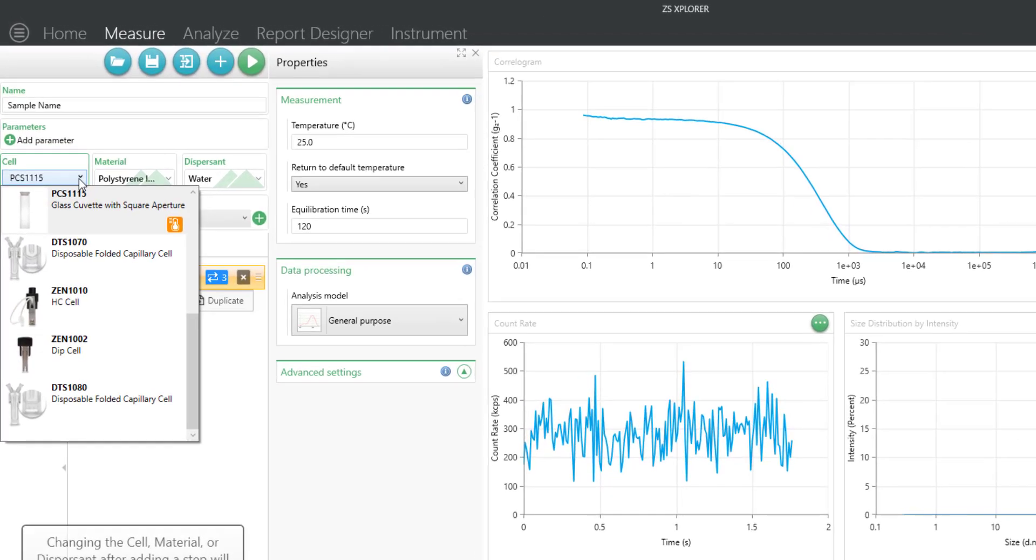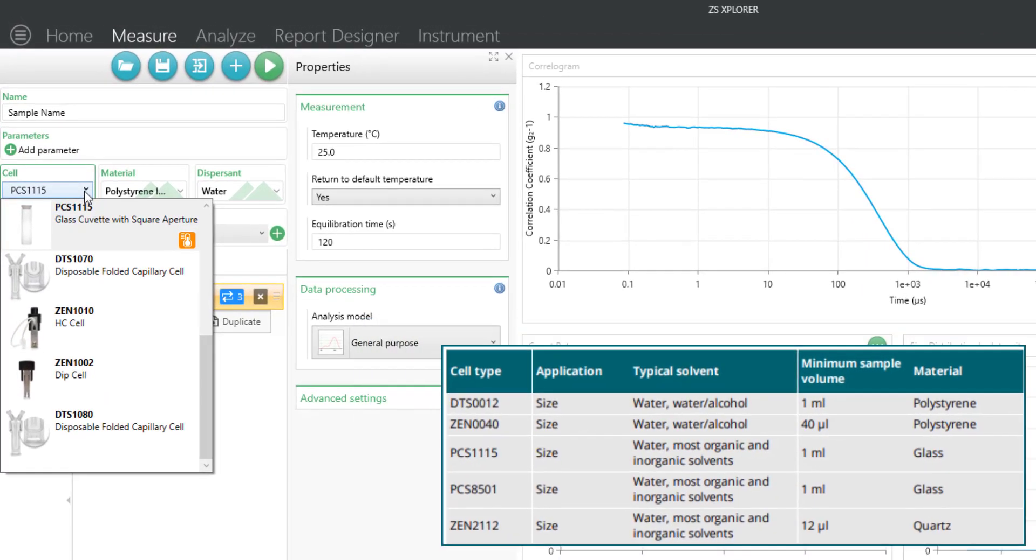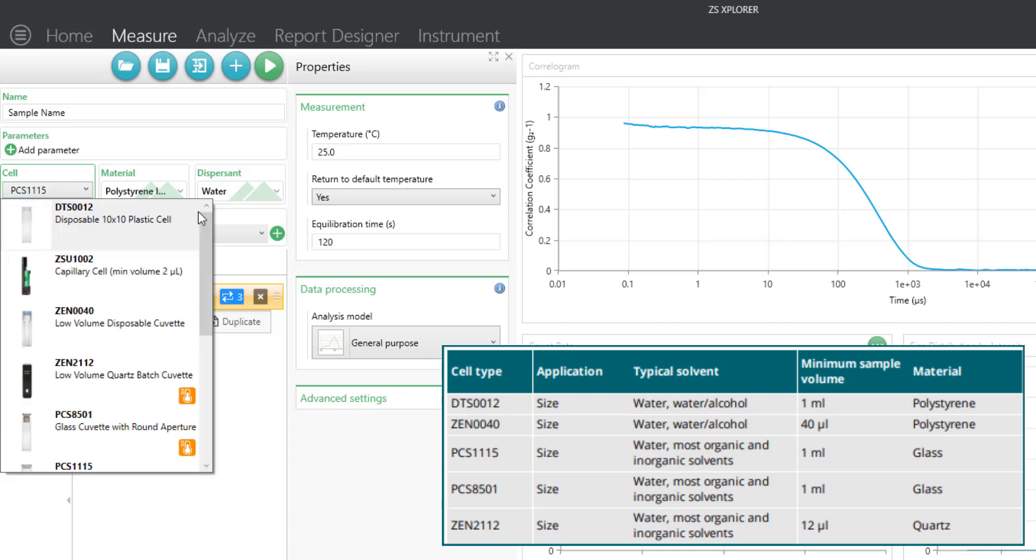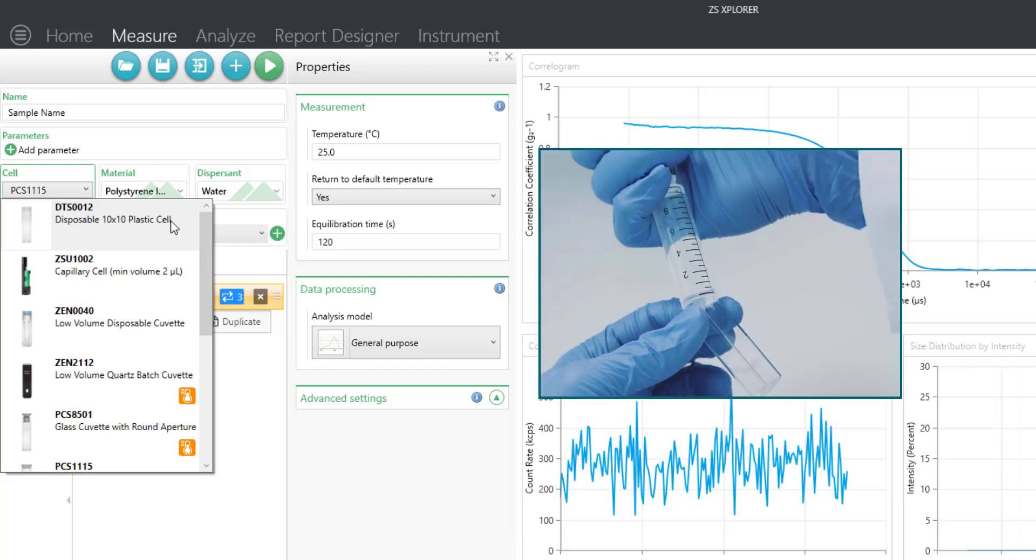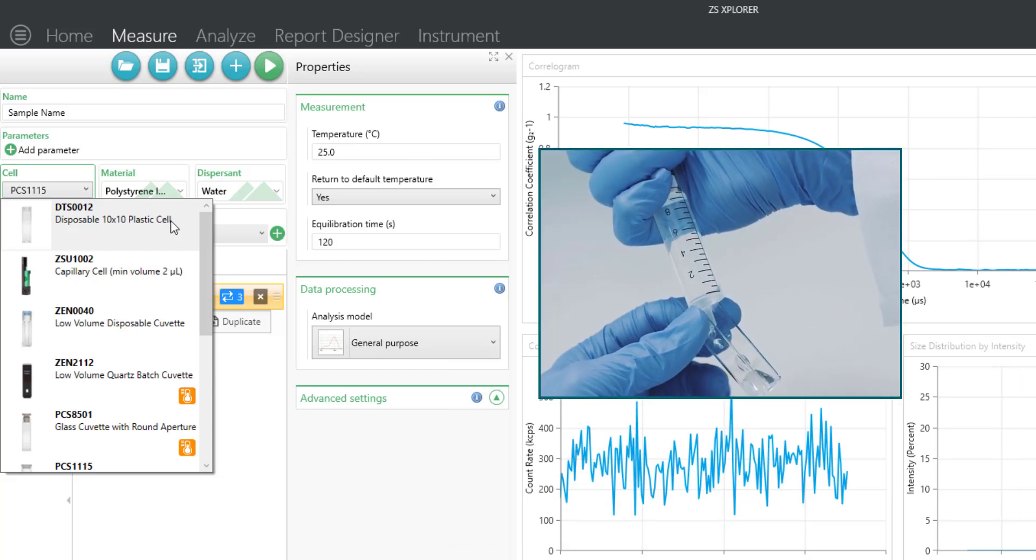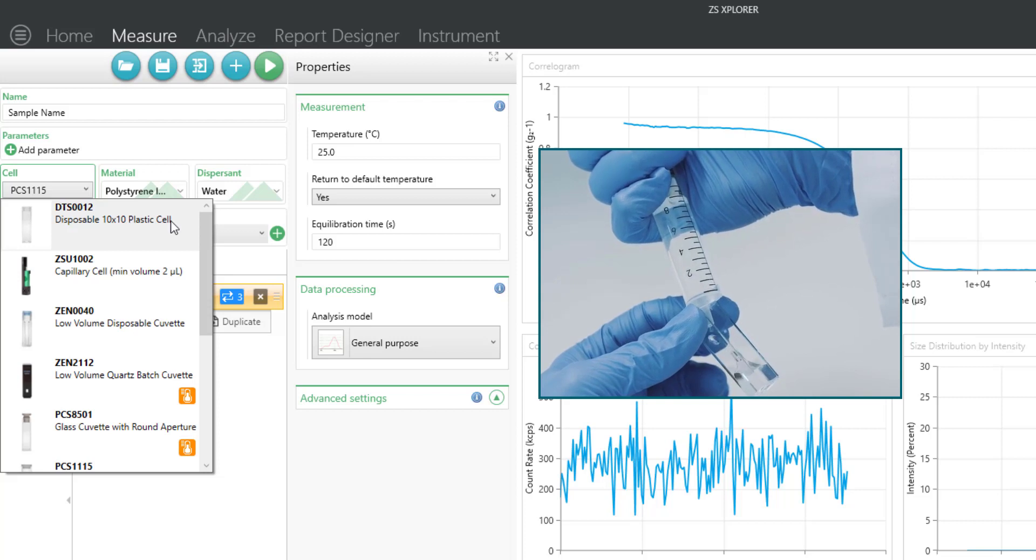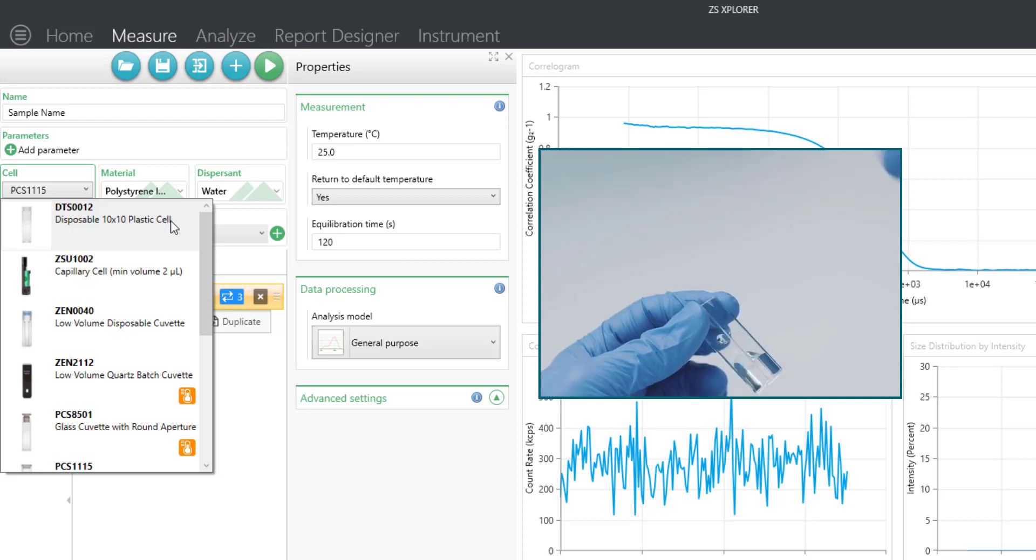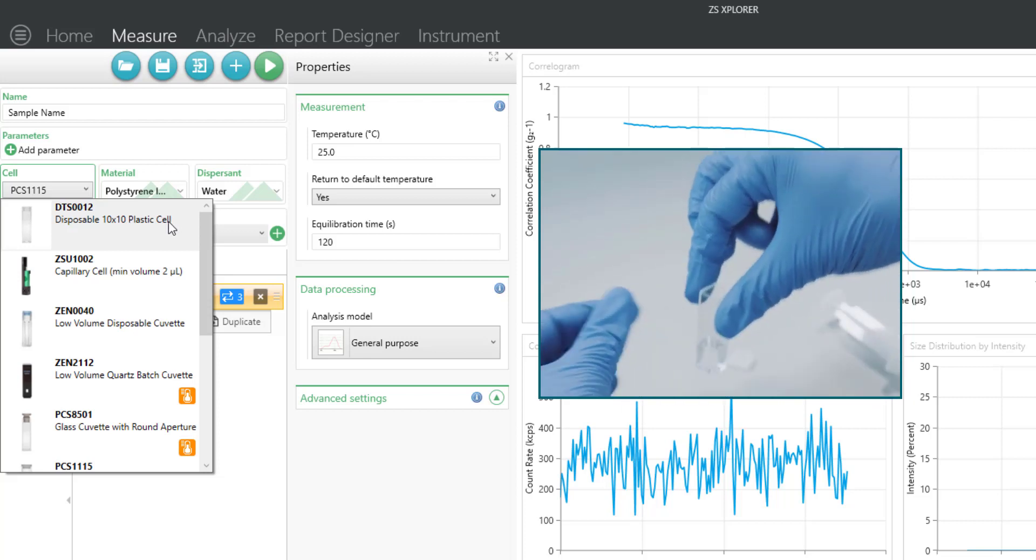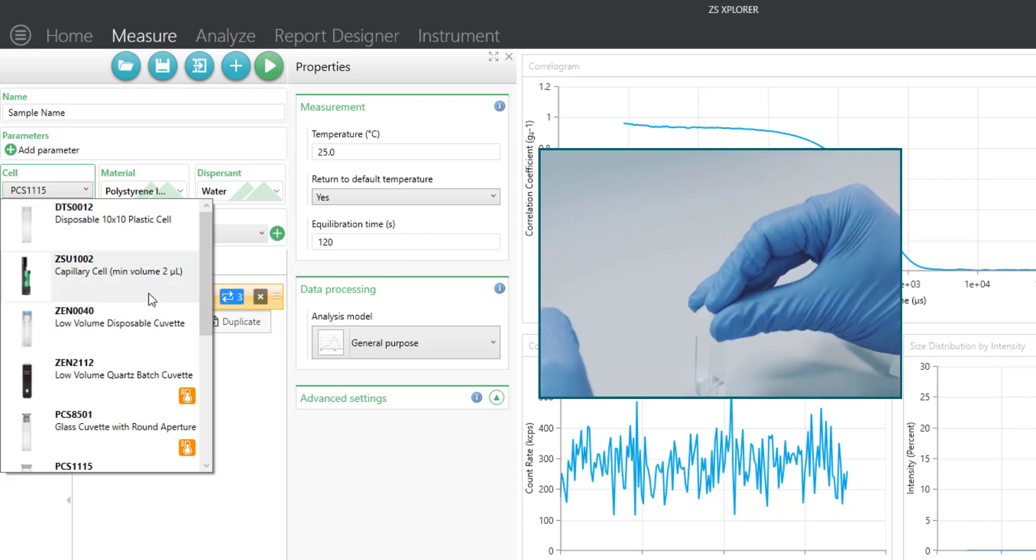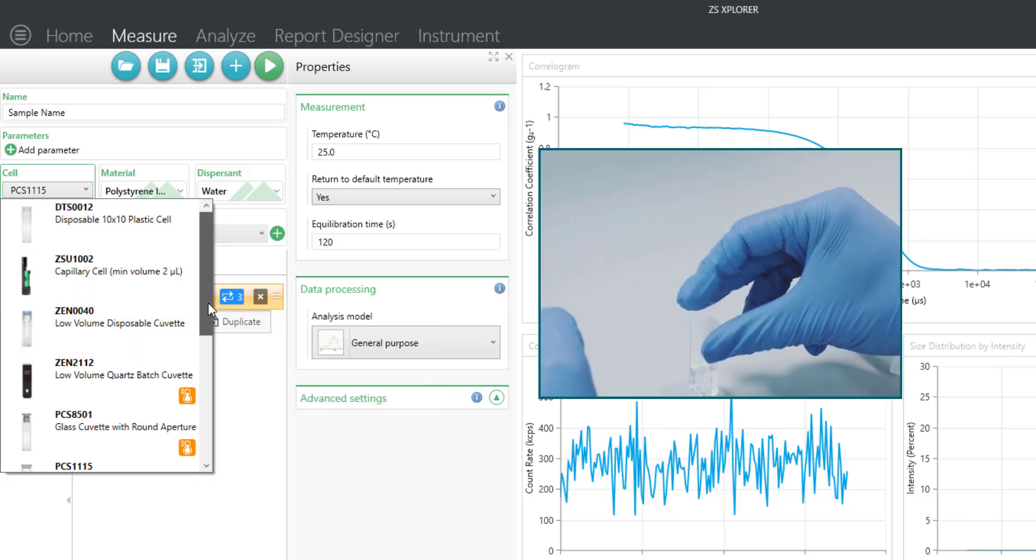Let's look at other cell types that might be available and the advantages or disadvantages of using them. In general, for sizing measurements, most people use disposable cells. This eliminates cross-contamination between samples, there's no required cleaning, they're a one-time use and throw away. These would be the disposable plastic cells that I've mentioned before.